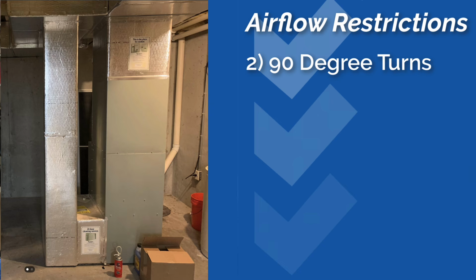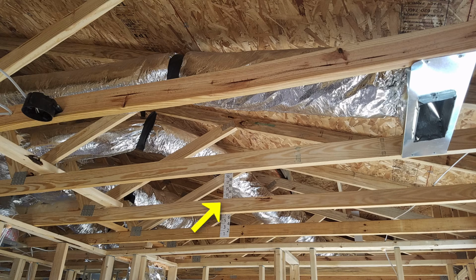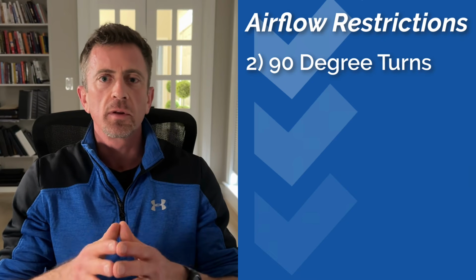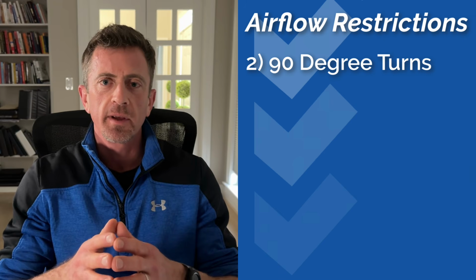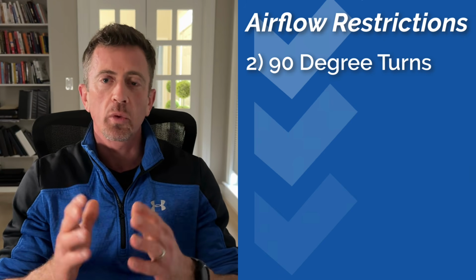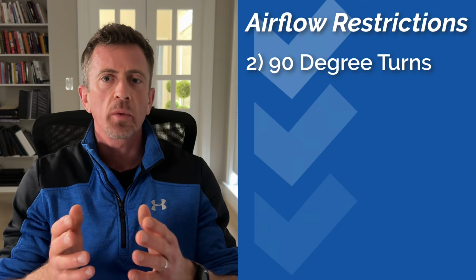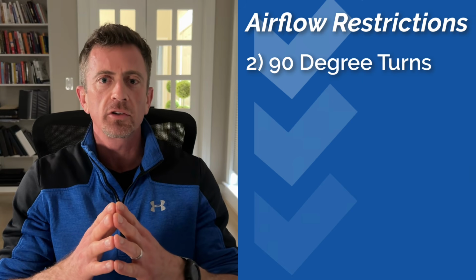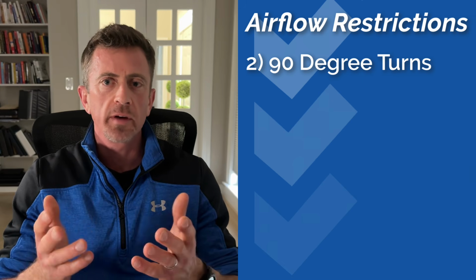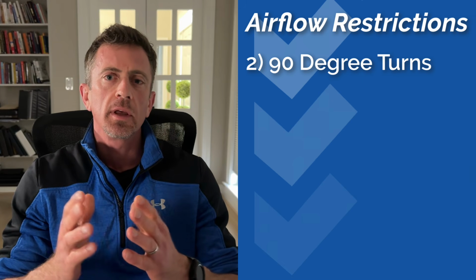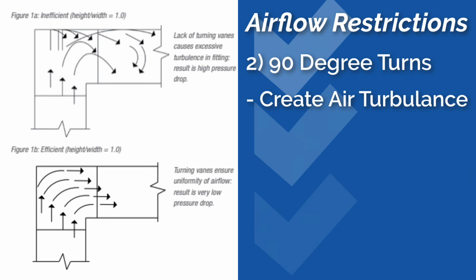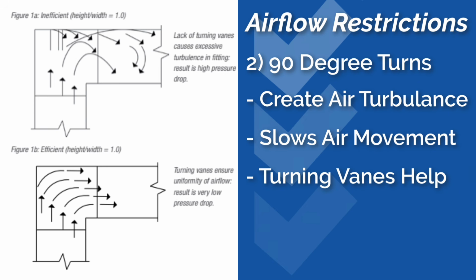The next restriction is a 90-degree turn. Sharp turns in any ductwork restrict airflow. Gentle curves are always better. Just think of airflow like a race car driver at the Indy 500. It can go over 200 miles an hour with wide sweeping turns, but the car would have to slow way down if it had to make sharp turns at every corner. Otherwise, it would spin out of control. In duct systems, those 90-degree turns create turbulence in the air, which is what slows down the air movement. This is where installing turning vanes actually comes in handy.